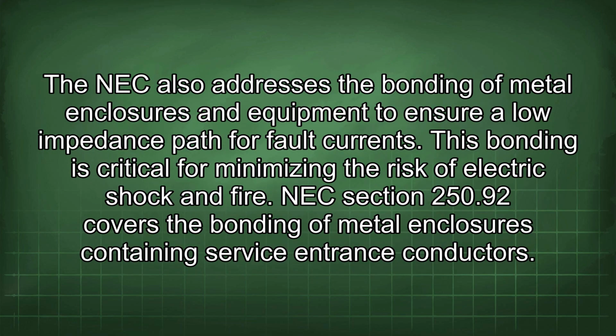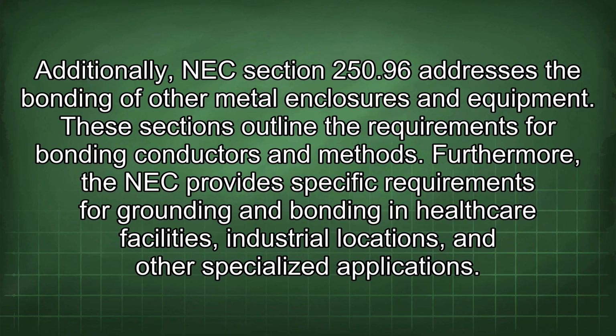The NEC also addresses the bonding of metal enclosures and equipment to ensure a lower impedance path for fault currents. This bonding is critical for minimizing the risk of electric shock and fire. NEC Section 250.92 covers the bonding of metal enclosures containing service entrance conductors. Additionally, NEC Section 250.96 addresses the bonding of other metal enclosures and equipment. These sections outline the requirements for bonding conductors and methods.